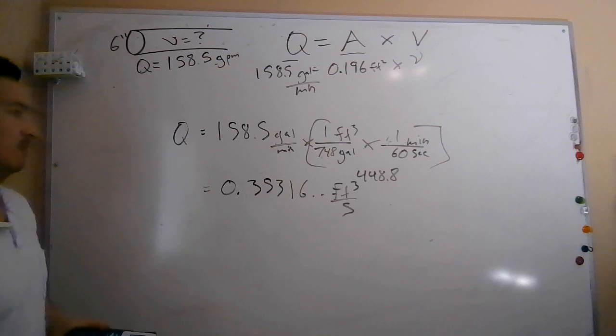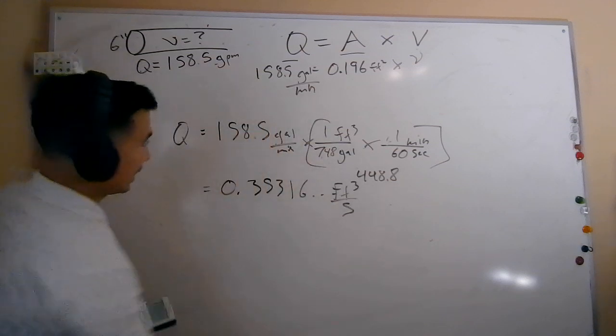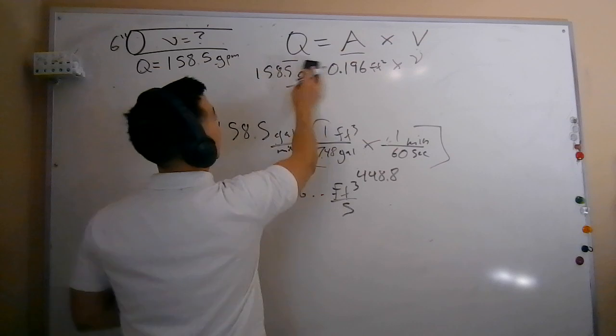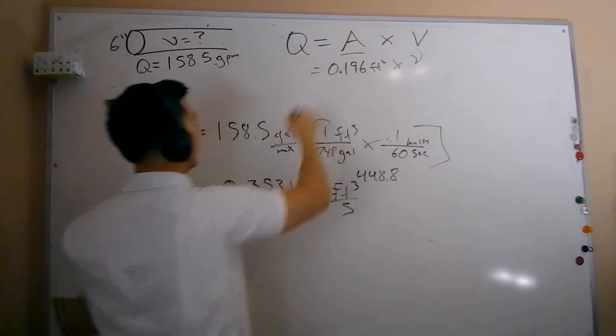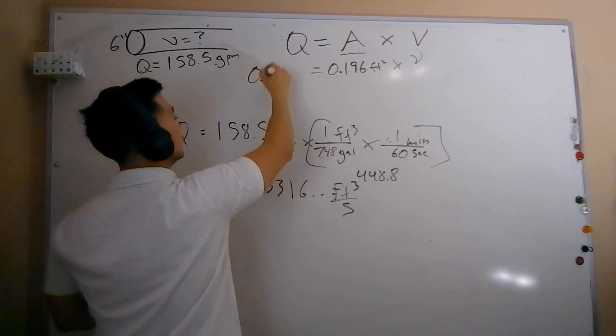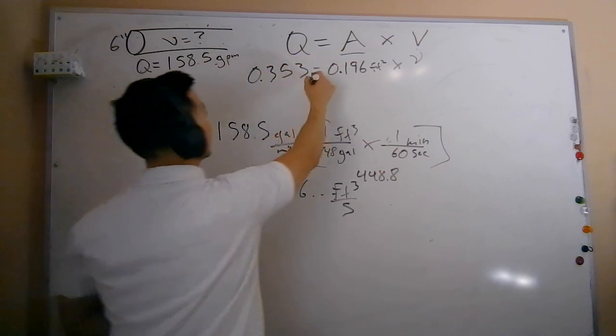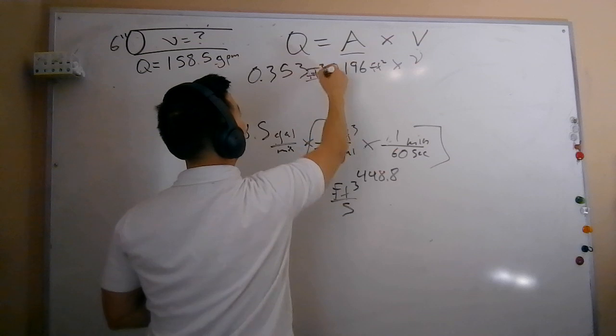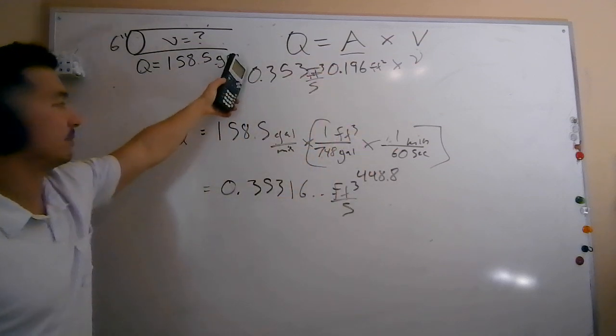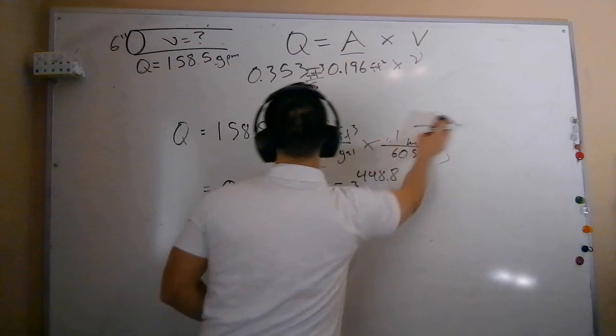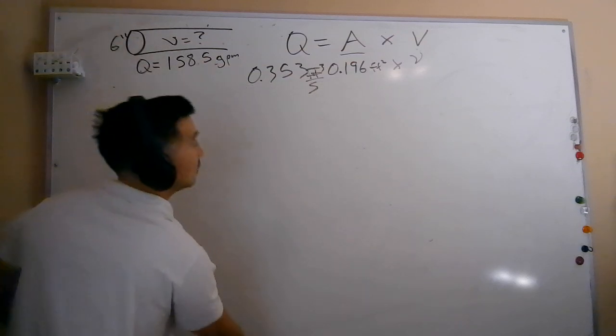That's what we want for this problem, cubic feet per second. So coming back up to the top here, if I rewrite out my flow rate now in CFS, we'll do 0.353. That's what I'll carry for the sake of this problem. Cubic feet per second. Now I'm just going to use this top formula. I'm good with the flow. Don't need this here anymore. And now I'm going to solve for velocity.